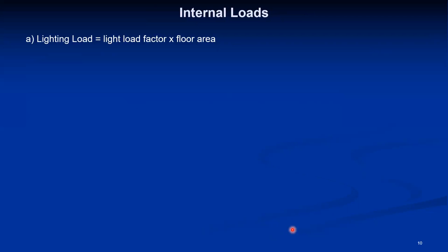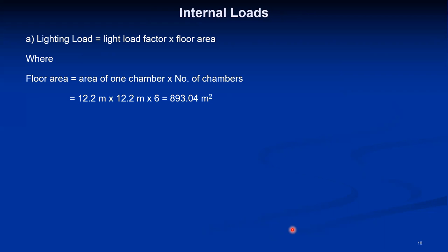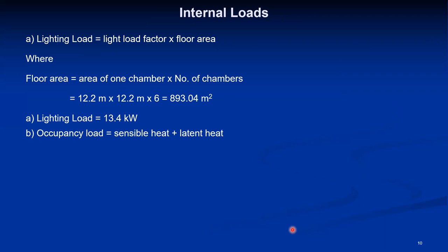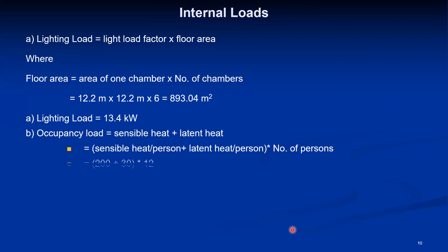The third type of load is internal load. The lighting load factor is given in the problem statement and also available in the design data book. Based on the floor area — area of one chamber multiplied by number of chambers — the total floor area comes around 893.04 square meters, and the lighting load comes around 13.4 kilowatt. The occupancy load, which is sensible heat plus latent heat from 12 persons at 200 Watt sensible and 30 Watt latent each, comes around 2.76 kilowatt. The total internal load comes around 16.16 kilowatt.